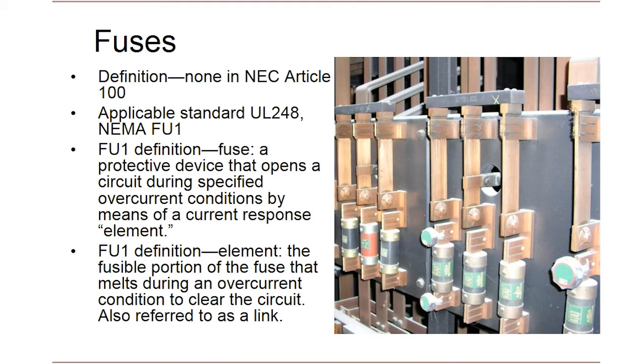Based on that definition, the question is: what is an element? NEMA FU1 describes the element as the fusible portion of the fuse that melts during an overcurrent condition to clear the circuit. Basically, it's a sacrificial conductor that melts — or even vaporizes depending on the magnitude of the current — when exposed to an overcurrent condition, opening the circuit to prevent damage to downstream devices.